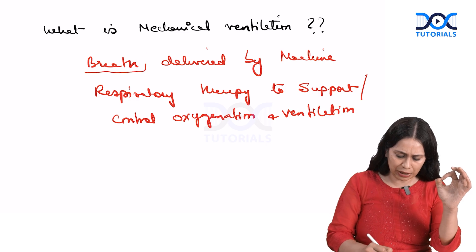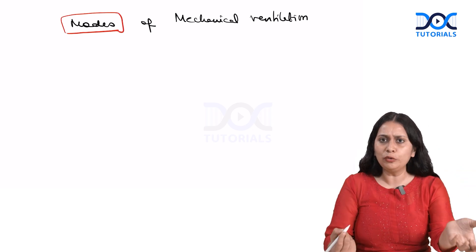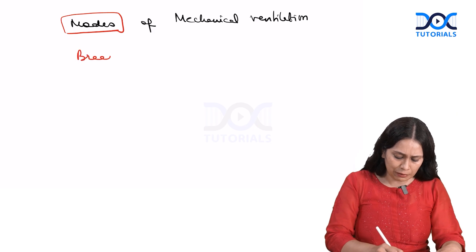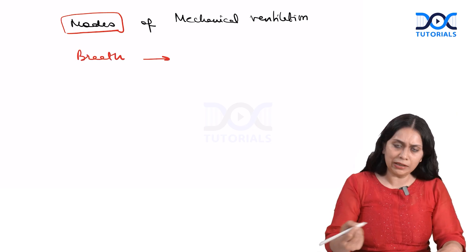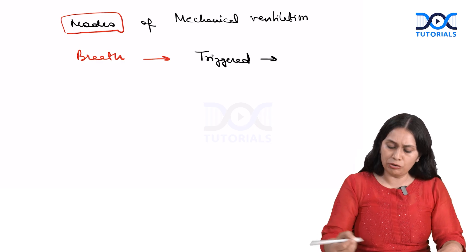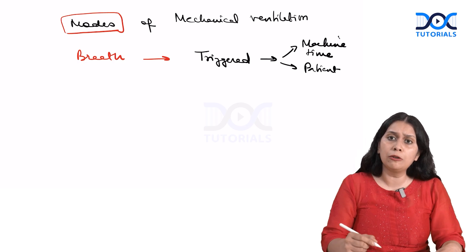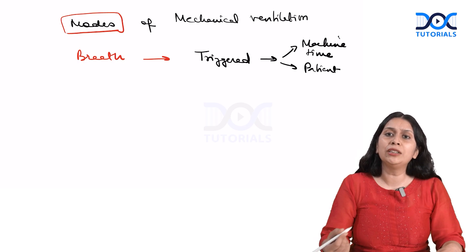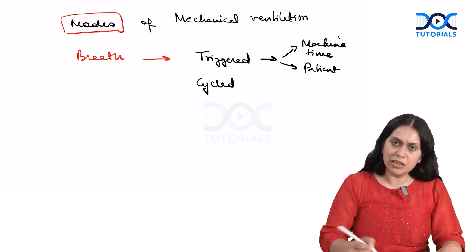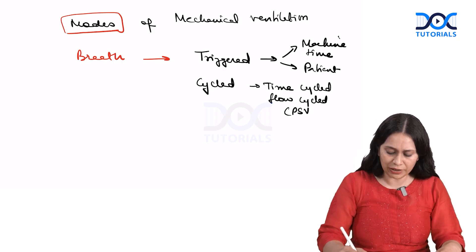How this breath is delivered to the patient depends upon the mode of mechanical ventilation. To understand the mode and how we select it, we need to understand what defines a mechanical breath. A mechanical breath is defined by how it gets triggered — either by the machine (time-triggered, controlled breath) or by the patient (patient-triggered, spontaneous or assisted breath). It is also defined by how it is cycled from inspiration to expiration — time cycle or flow cycle. Most modes are time-cycled, except PSV (pressure support ventilation), which is flow-cycled.